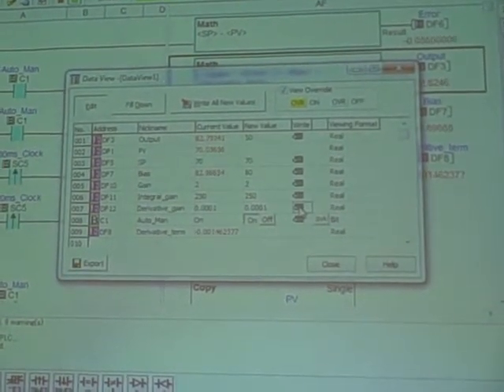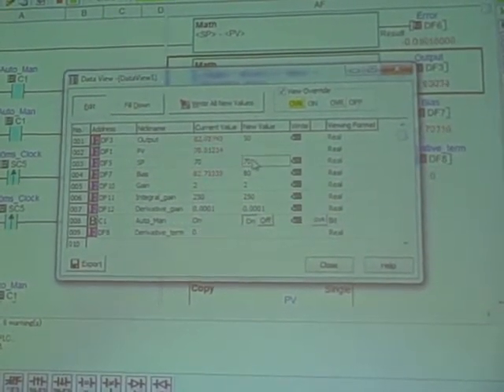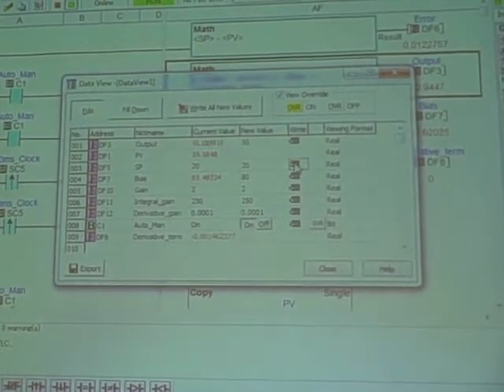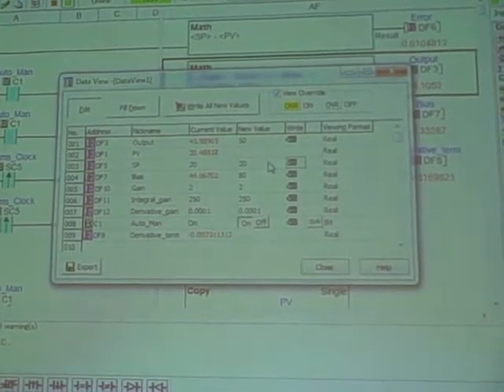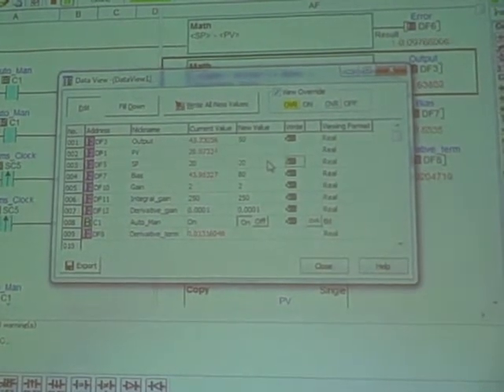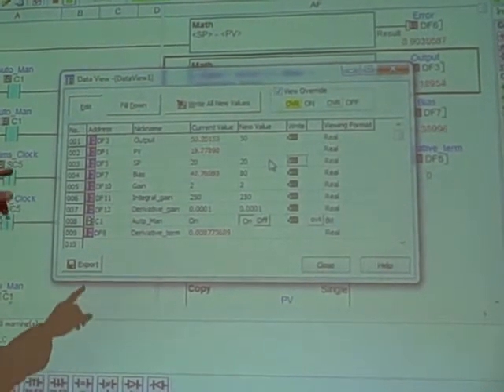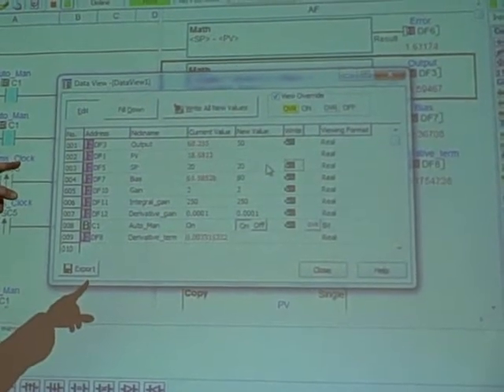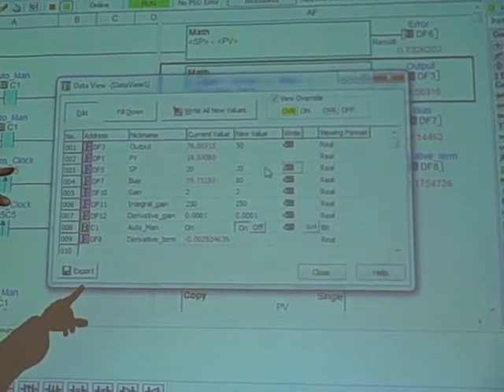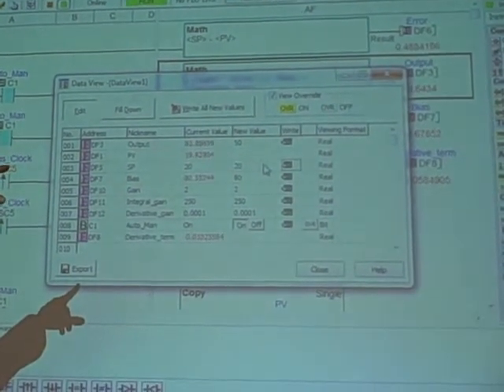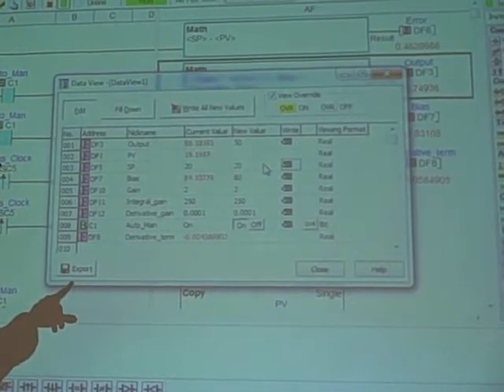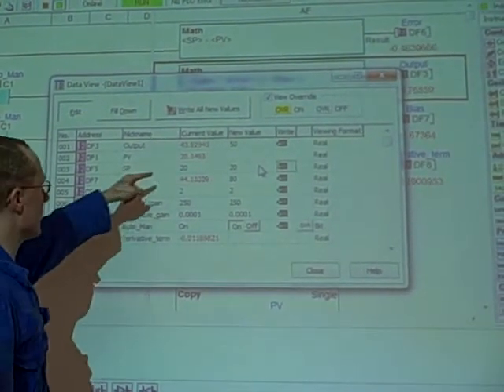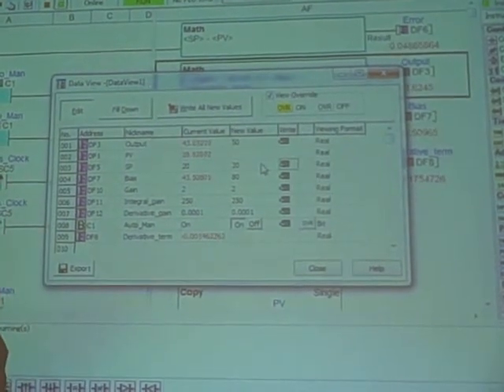I'm going to move this setpoint down to a lower value, like 20%. Now if I try to slow this down with my finger, we're going to see the output rises very rapidly. Process variable is hanging about 18.5%. It does a very good job of controlling motor speed. When I let go of the motor with my finger, we overshoot briefly, comes right back into control and settles at a setpoint of 20%.